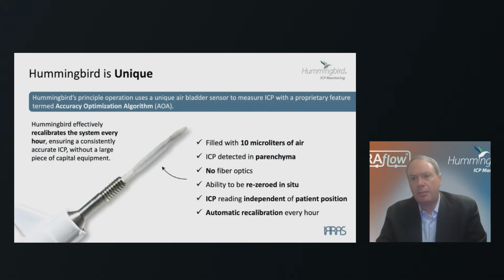Hummingbird is unique compared to other commercially available systems because of its mechanism of action. Hummingbird uses a small air bladder on the distal tip of the probe that's filled with a small amount of air, approximately 10 microliters. That air bladder is inserted within the brain tissue, the parenchyma, and the brain tissue exerts pressure onto that air bladder.